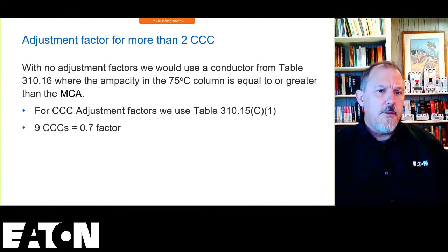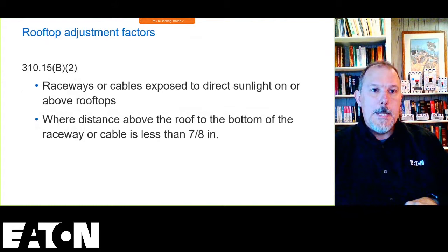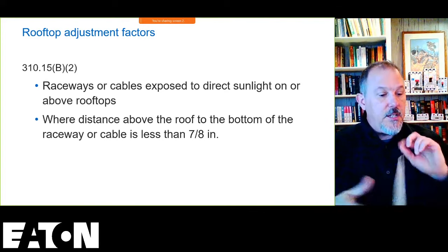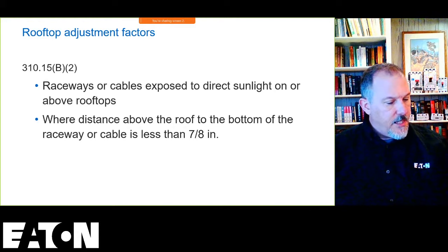So I would just consider nine conductors and I come up with a 0.7 factor, 70%. All right. And then the rooftop adjustment factors, that's your 310.15(B)(2). So I'm going to read that one for you.